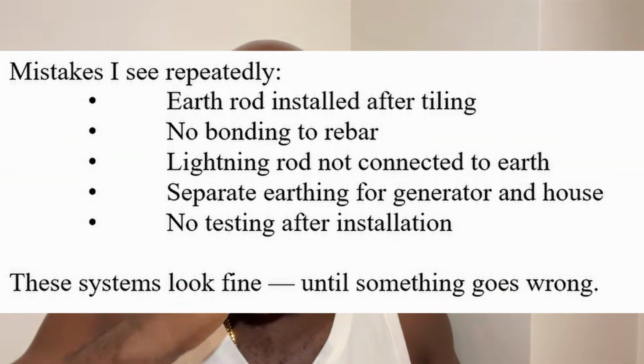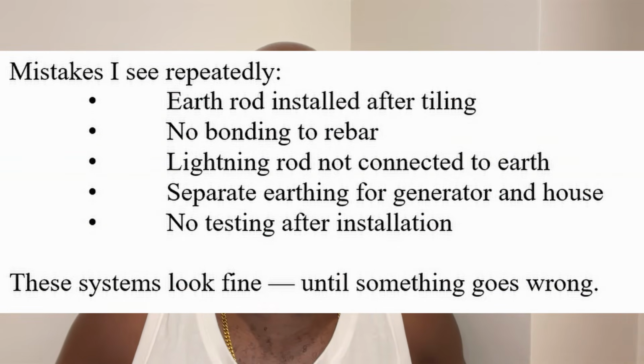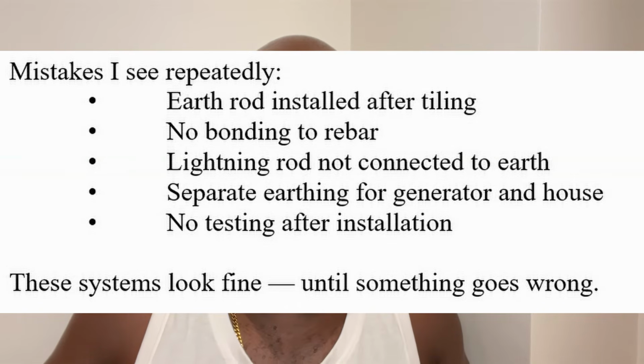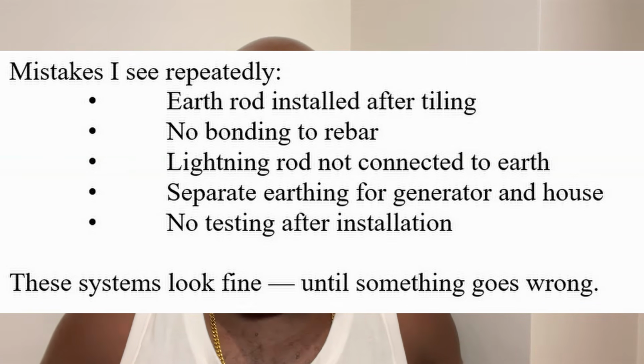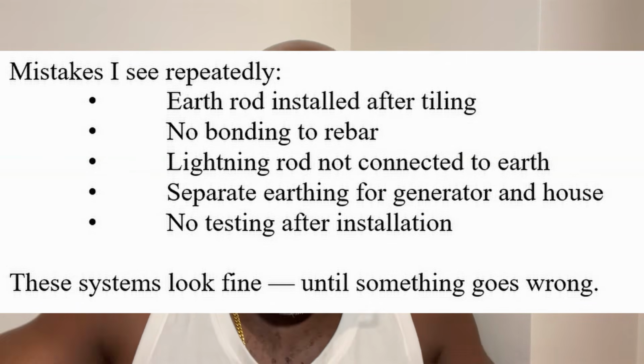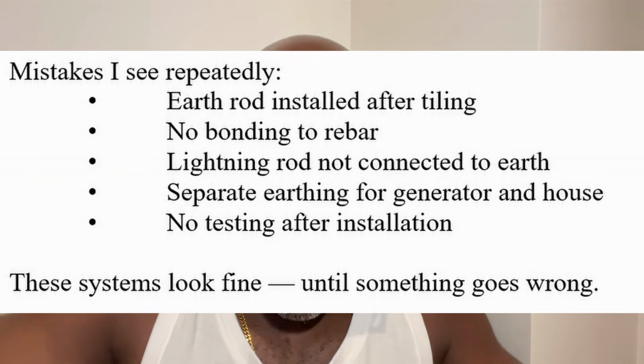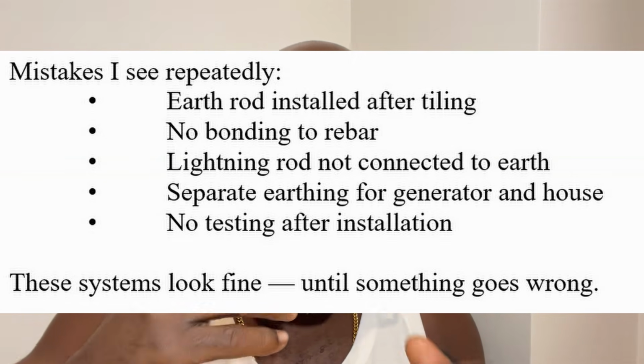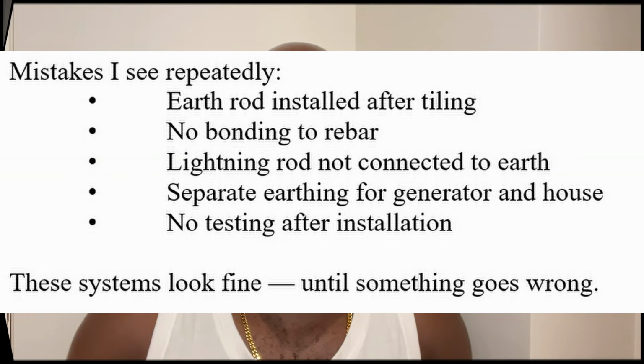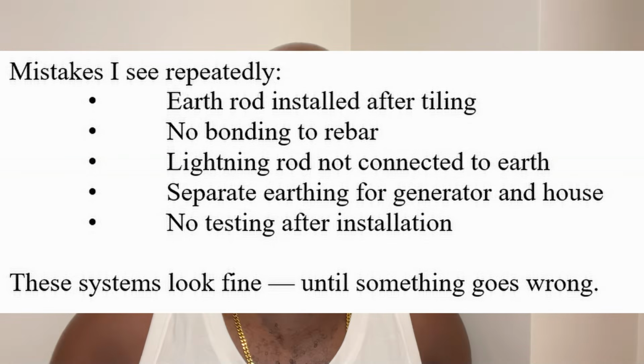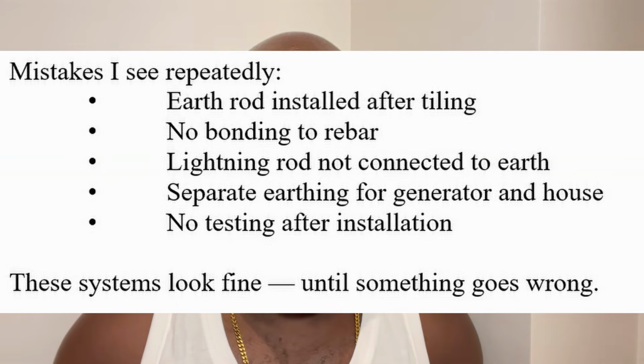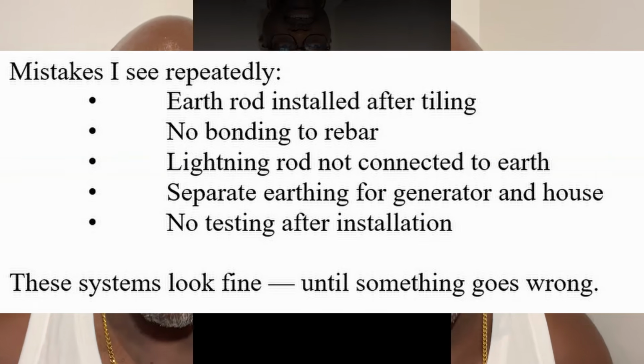Mistakes that I see occasionally in some homes: the earth rod is installed after tiling. Well, how are you going to bring the earth cable in? There's no earth bonding to the reinforcement rebars that are in the building structure. The lightning rod is not connected to the earth. Separate earthing for the generator and the house. No testing after installation. The system looks fine until something goes wrong.